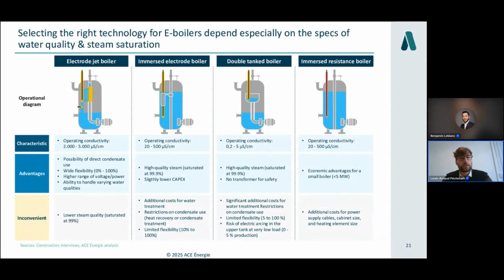The first thing is what the different technologies for e-boilers are. There are mainly four of them. The first three are electrode boilers. The first one is a jet boiler. The second one is the immersed electrode boiler. The third one is the double tank boiler. The last one is an immersed resistance boiler. So there is no electrode, it's the resistance.